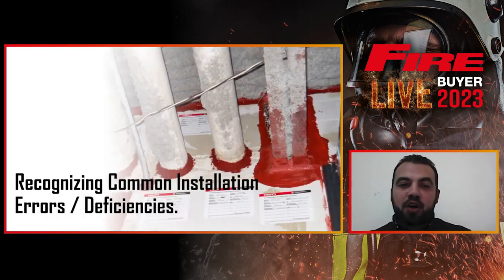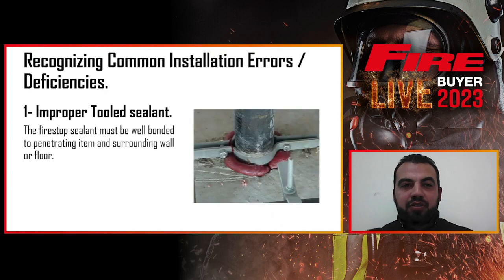Recognizing the common installation errors and deficiencies is what you need to avoid on site, and what the fire inspector needs to look at when doing the inspections. The first case here is the improper tooled sealant. This gives an indication that your material is not installed with the right thickness in the annular space, and that the annular space might not be filled properly.